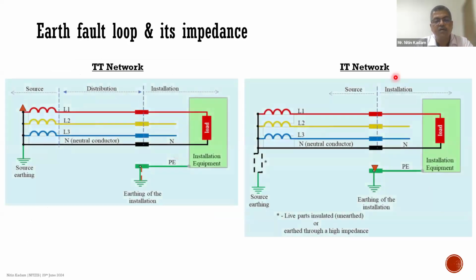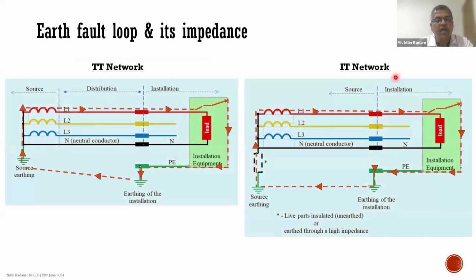In case of TT network, you do not have a direct connection between the two earthings which are here, which is the source earthing and the localized earthing on the site. And therefore, the fault loop impedance test will not pass in case of TT network as well as the IT network here, because there is no direct bonding or metallic connection between these two points.